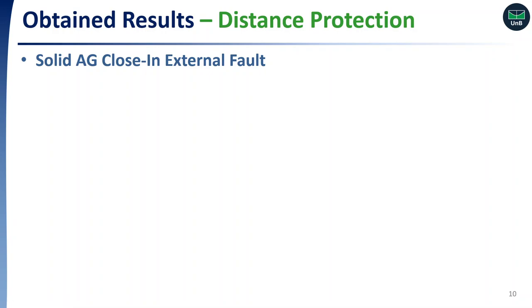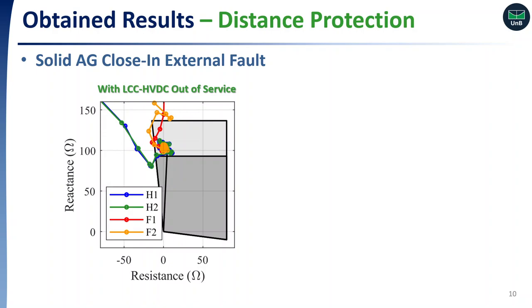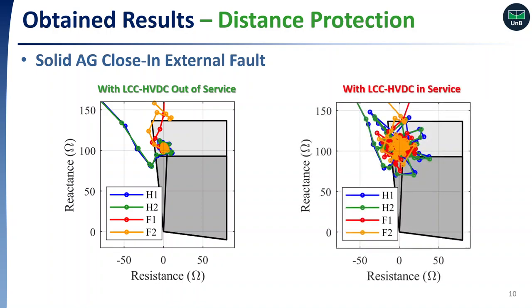Here we can see the results for distance protection. First, when both LCC-HVDC bipoles are out of service, only AC infeed current flows through the system. In this way, the performance of the distance protection was as expected, such that the fault is seen in the second zone of the relay installed at the Araraquara 2 station. However, if both LCC-HVDC bipoles are in service, the AC waveforms become quite distorted, mainly when commutation failures take place. Therefore, errors in the phasor estimation process arise, leading Zone 1 to detect the fault, and a false trip may be issued.